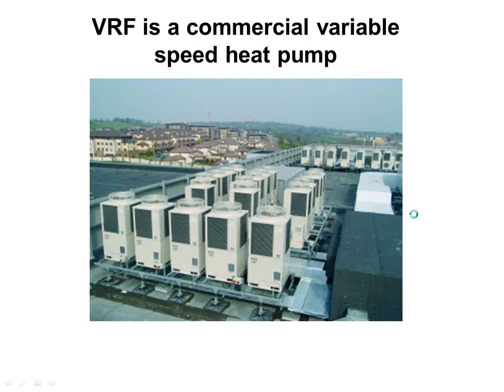But just to kind of give you a quick overview, if you're not familiar with variable refrigerant flow systems, basically you have outdoor units that are heat pumps. You can have 1, 2, or some cases 3 of them manifolded together working as a team, if you will. Each one of them has 2 or 3 compressors in it. So I got lots of compressors and capacity stages. Those compressors, at least one of them in each unit is variable speed. Sometimes all of them are variable speed. They are inverter driven like we just talked about.